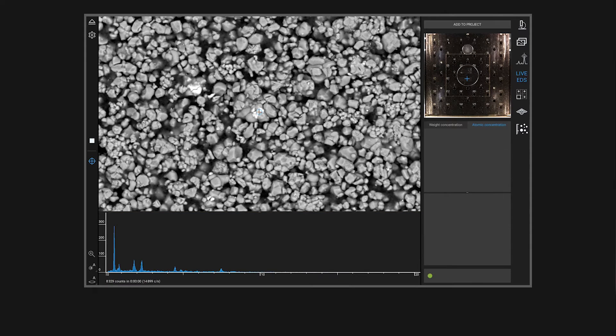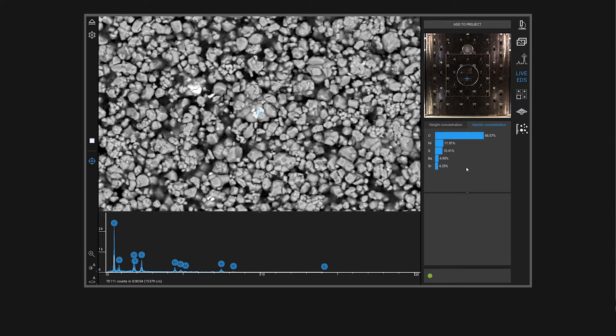With the live EDS functionality we can click on the particle and in a few seconds we will see on screen what is the chemical composition of the contaminants that we are analyzing. The technique is extremely fast and gives us very accurate information. We don't need to adjust any additional parameters because the design of the Phenom is completely embedded in the quantification software, so the microscope will make sure to adjust all the parameters for you.